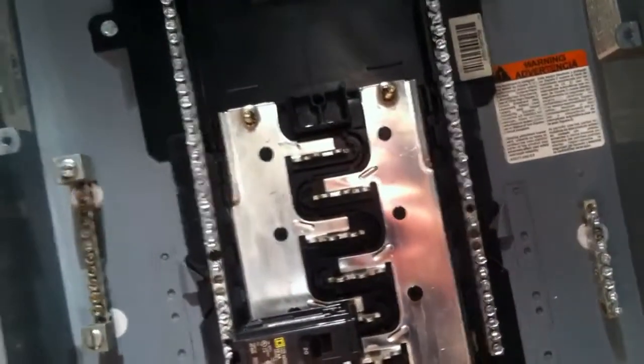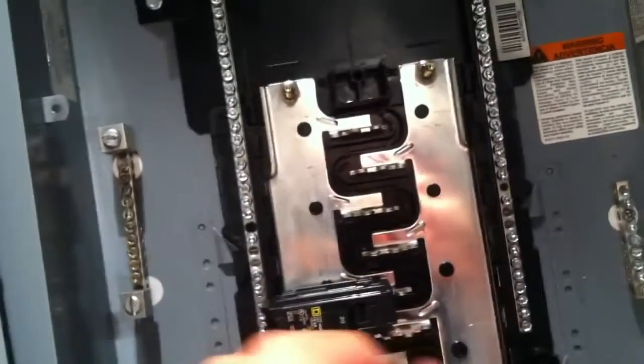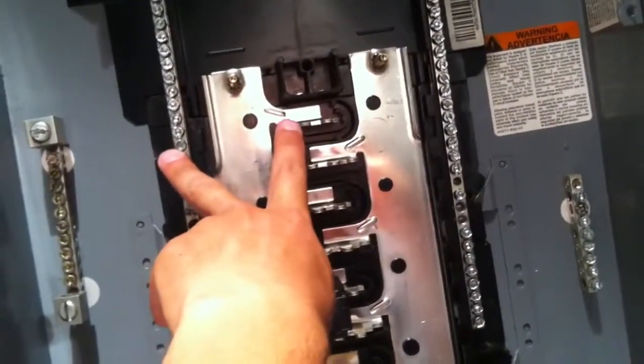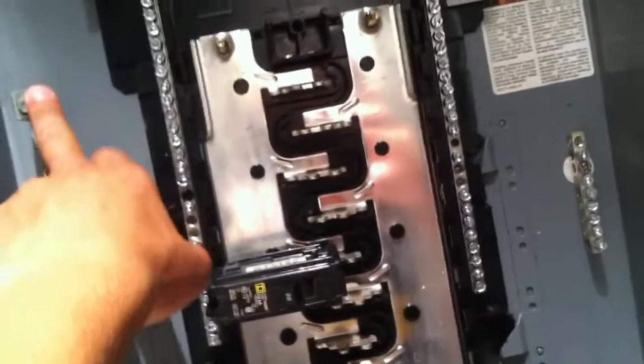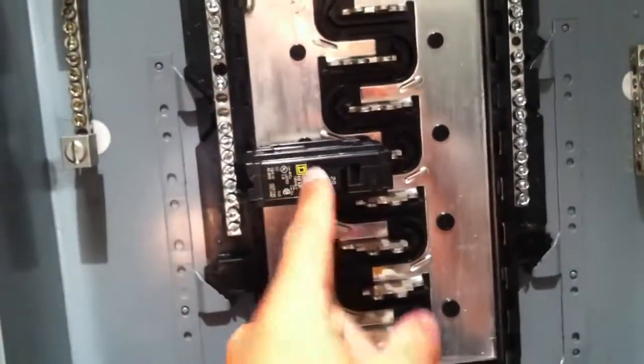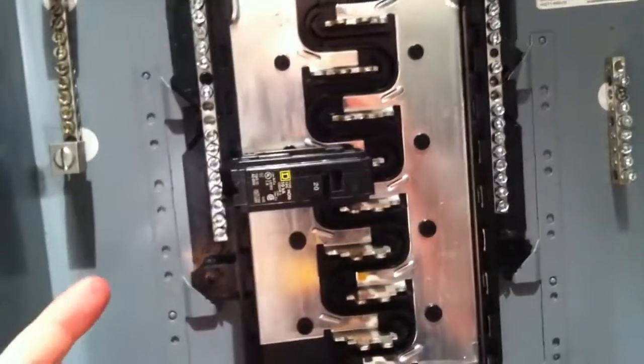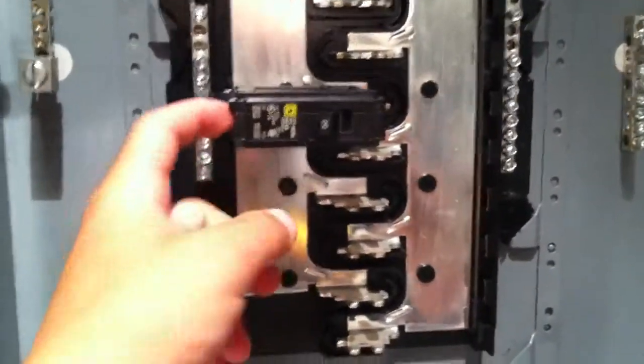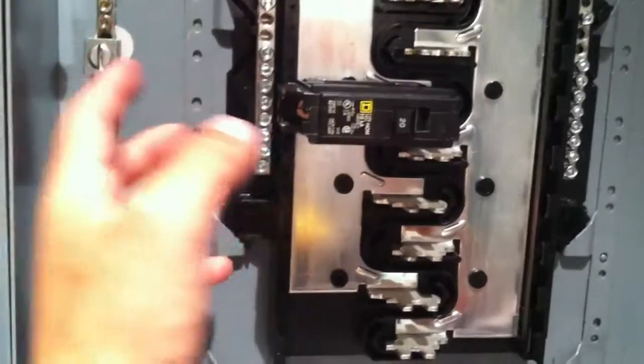Ground faults are a lot more sensitive. They trip at about 5 to 10 milliamps. So if they detect 5 milliamps of current that's not coming back through this neutral line, they shut off immediately. That means it's going through the ground line. Okay, so that's the difference between those. These others just detect how much current is flowing. They don't care where it comes back through. They don't care if it goes to the ground. They don't care if it goes anywhere. They just care how much current is flowing through that line.